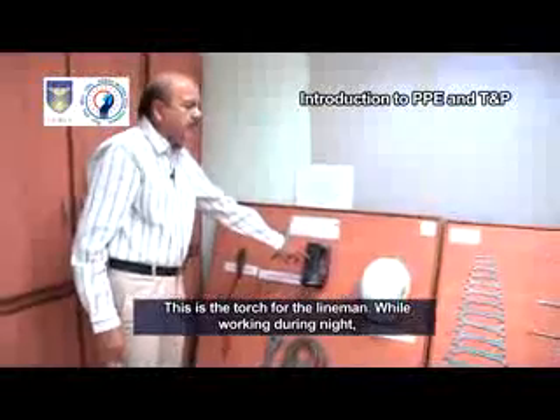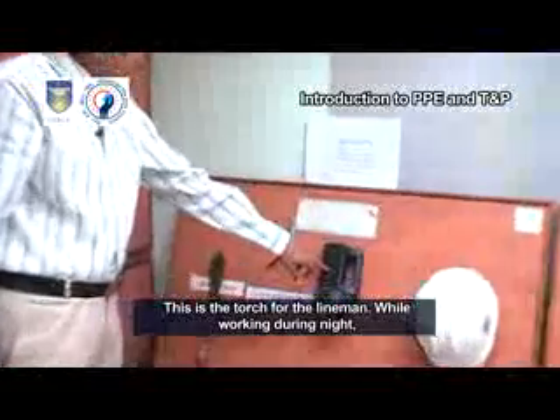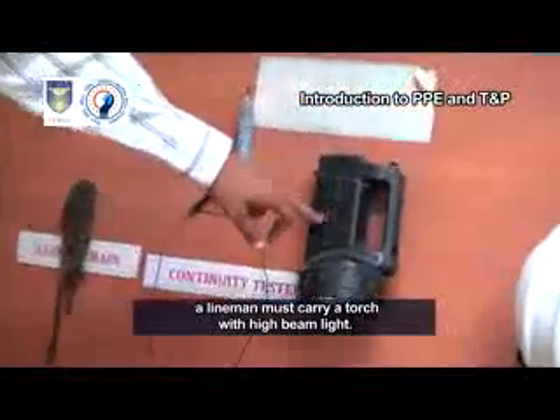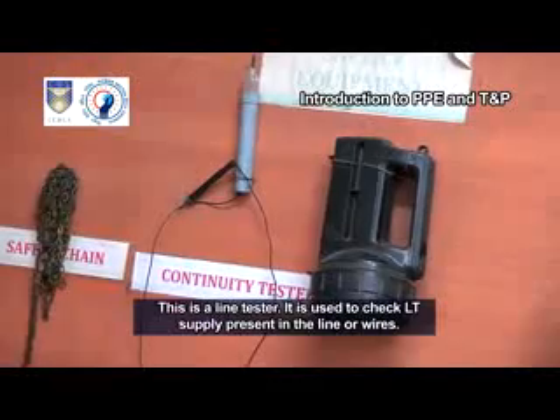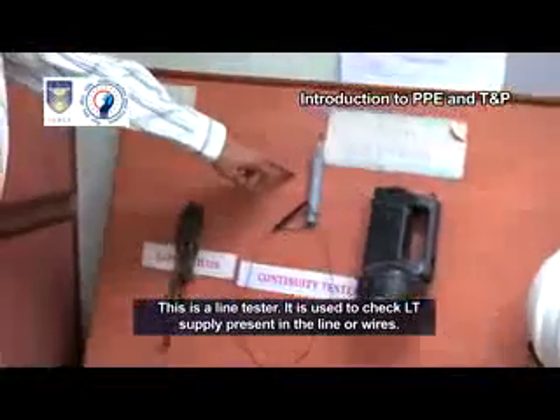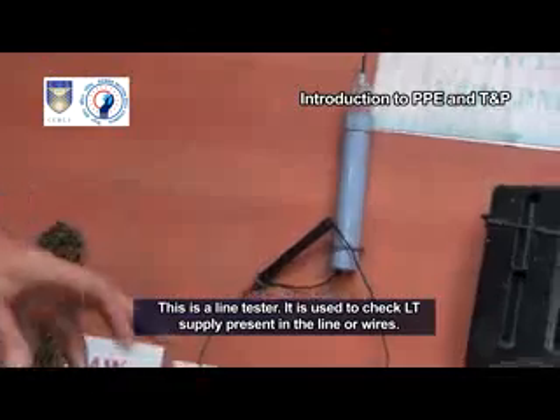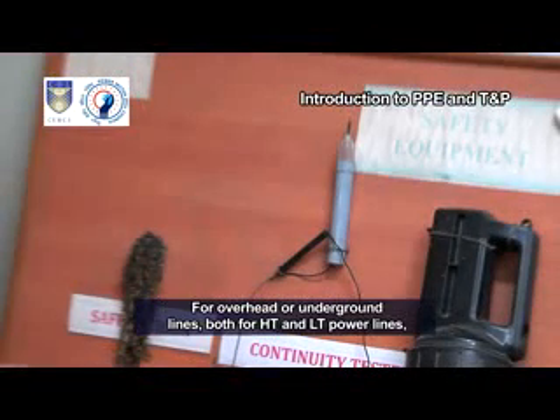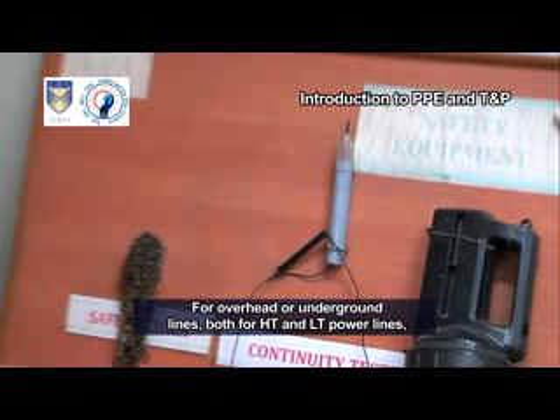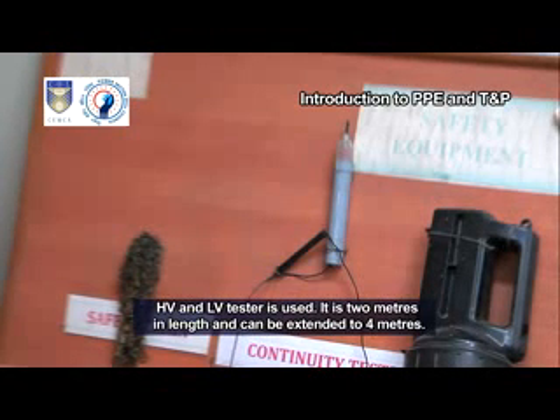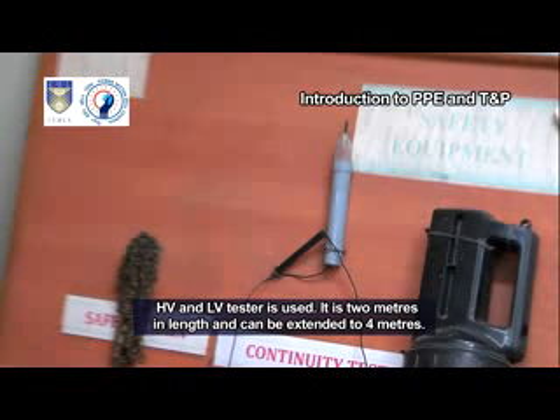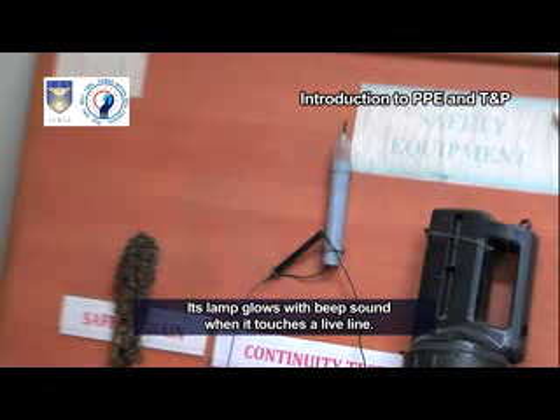This is the torch for the lineman. While working during night, a lineman must carry a torch with high beam light. This is a line tester. It is used to check LT supply present in the line or wires for overhead or underground lines, both for HT and LT power lines. HV and LV tester is used. It is 2 meters in length and can be extended to 4 meters. Its lamp glows with a beep sound when it touches a live line.